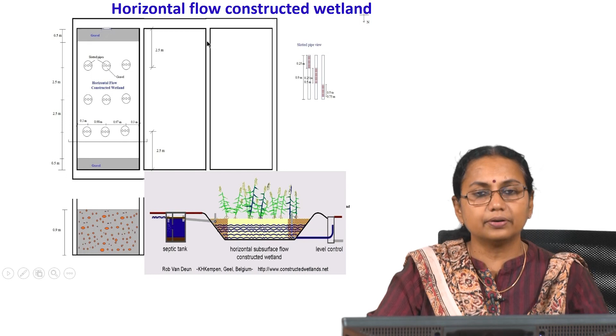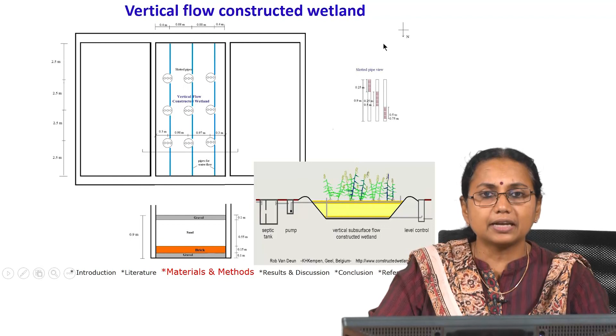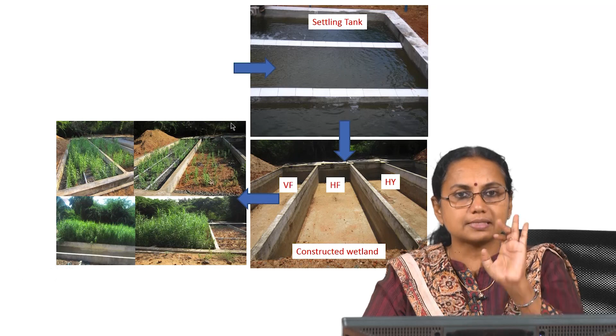So, this is the constructed wetland, around 10 meters long and 2.5 meters wide. We have put it in a hostel, and you can see that the plants are growing very well. What you have to do is have a settling tank, so that any settleable solids will settle, then allow the water to pass through the constructed wetland. All the pollutants will be removed by the combined action of physical, chemical and biological processes, and you will get clear water. This water can be used for flushing purposes, gardening purposes and so on.